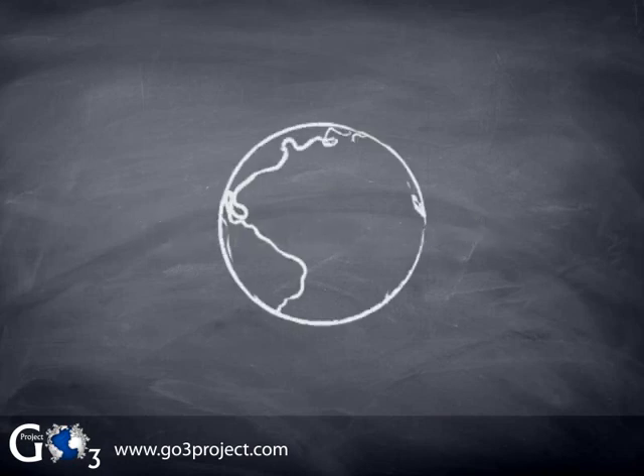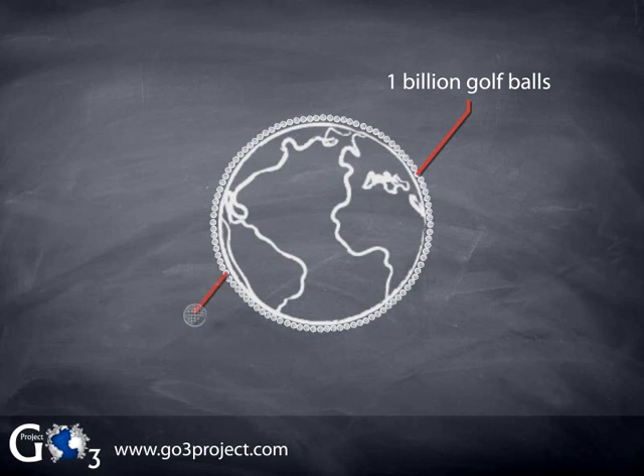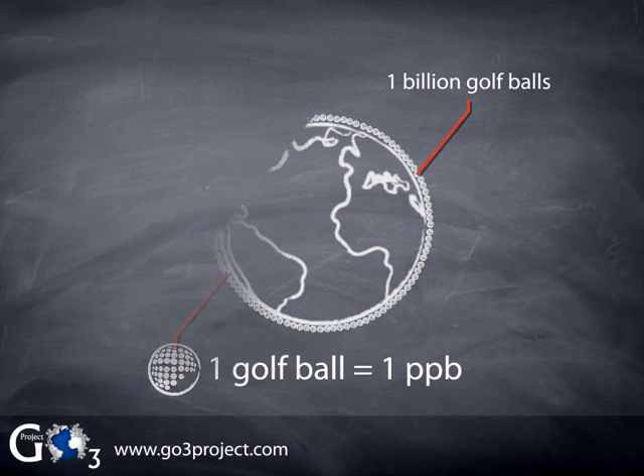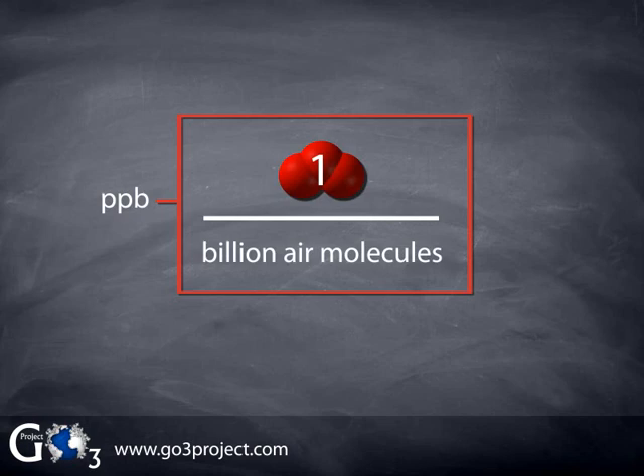To visualize what one PPB is, consider circling the earth with golf balls. It would take one billion golf balls to surround the earth at the equator. One golf ball then represents one part per billion, or one PPB, of the golf balls. Ozone monitors are capable of measuring ozone with a precision and accuracy of about one PPB. A level of one PPB of ozone means that there is one ozone molecule for every one billion air molecules. Since PPB is the fraction of air molecules that are ozone, to express ozone in PPB units, we need to know the concentration of air molecules.